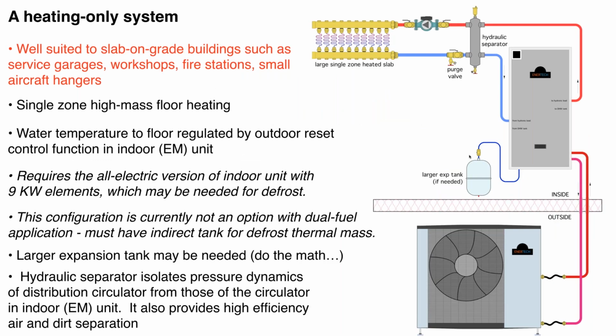Now, there are going to be some special applications, one of which is a heating-only application. Some examples of that could be a residential application, but more typically, it might be something like a firehouse, ambulance garage, maybe a commercial garage type structure, okay? And those are ideal for floor heating. Low temperature floor heating is going to allow that heat pump to perform well. The unit that I'm showing here would be the electric unit, okay? So again, it has that built-in auxiliary heating.